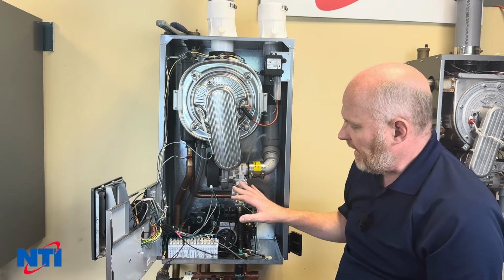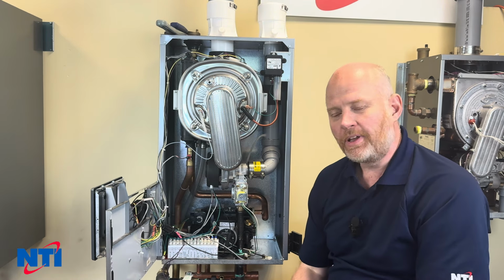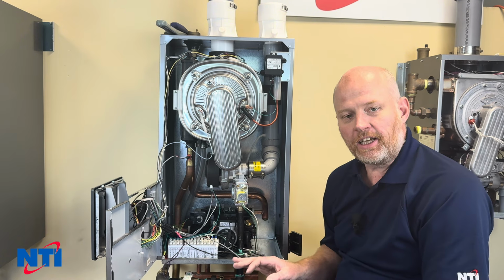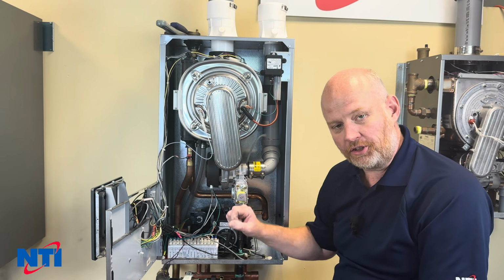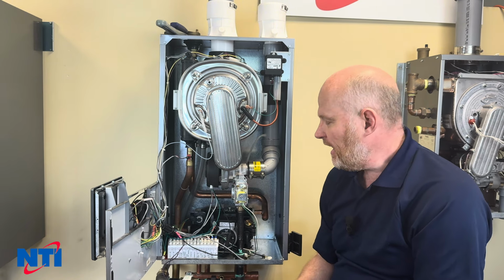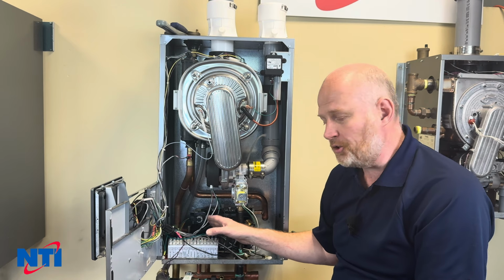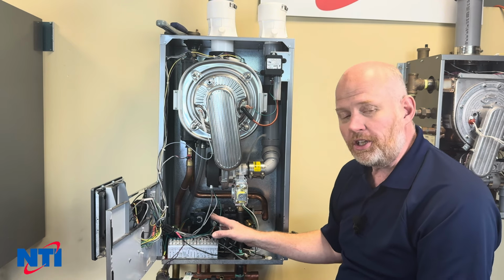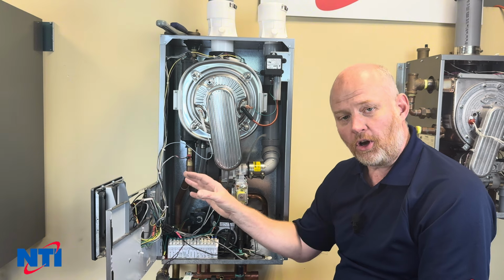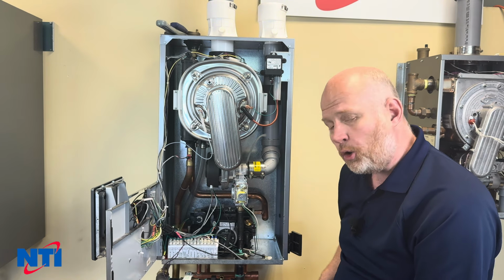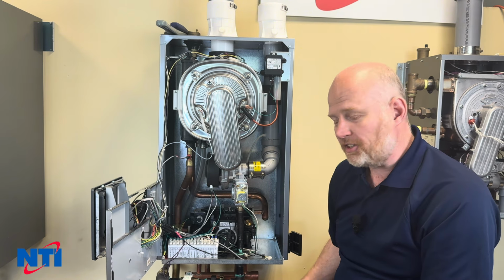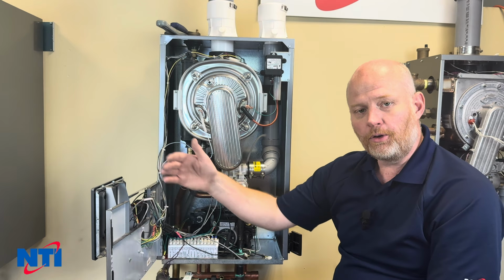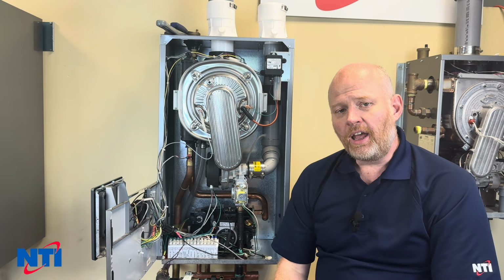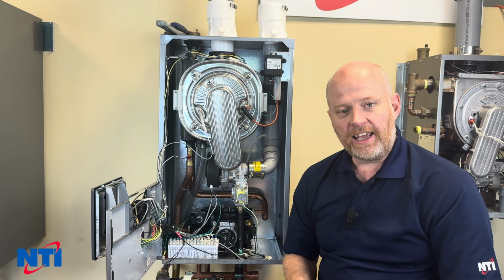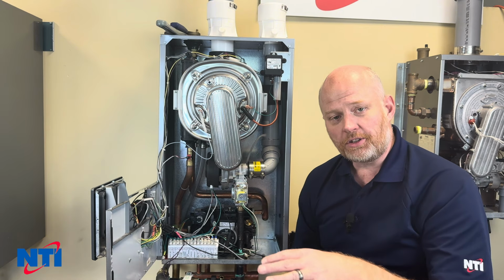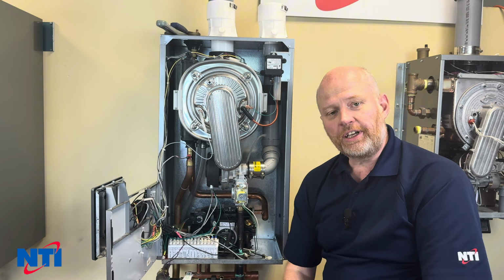Now that we have this buttoned back up, you want to refill your boiler. It's important that when you refill it, that you don't, on the domestic water side, just turn the cold water back on. That can actually damage the flow sensor in the boiler. What you want to do when you fill this is you're going to open the hot water fixtures, slowly open the cold water for the domestic to allow it to fill the boiler and fill the hot water lines with water. Once that's done, you can then close the hot water taps and reintroduce water into the boiler.